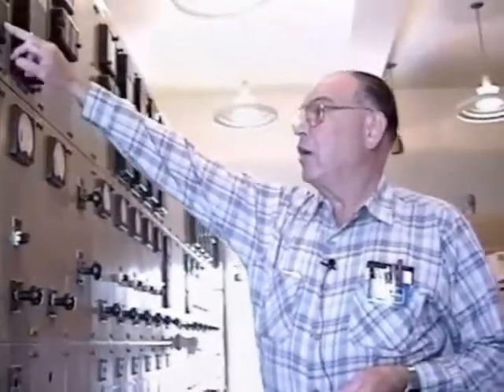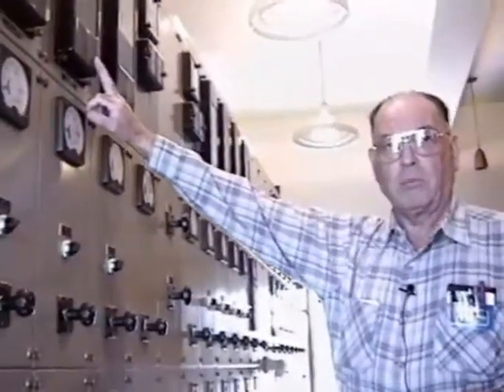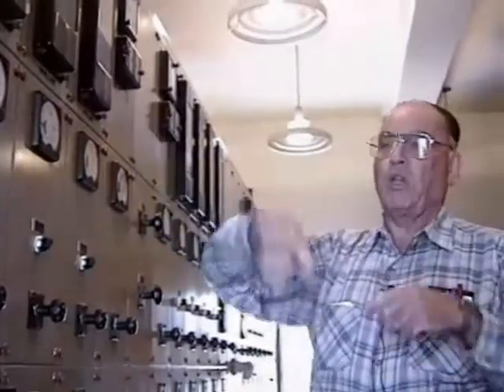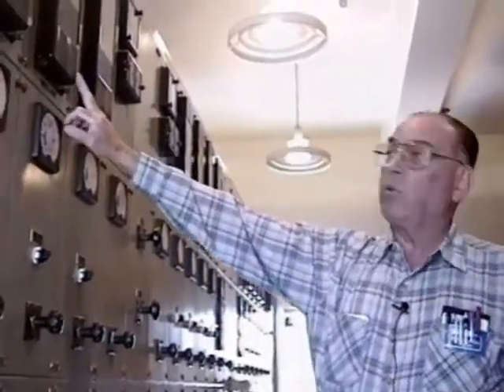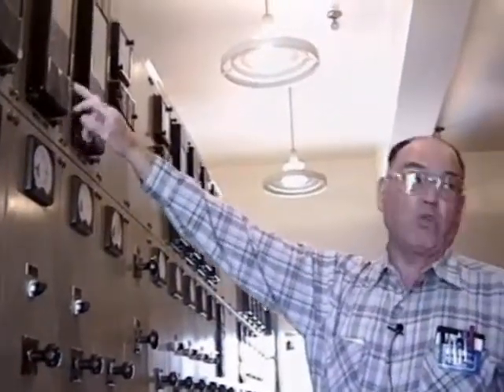We have reclosing relays here, one of the things I have to put back pretty soon. If a tree branch or something slaps wires together, the probability is it will clear, so this will try twice to close that circuit breaker again and turn the lights back on. If something's still there, it does what we call lockout, and it won't try to close again. I have to come back and put it back in manually.